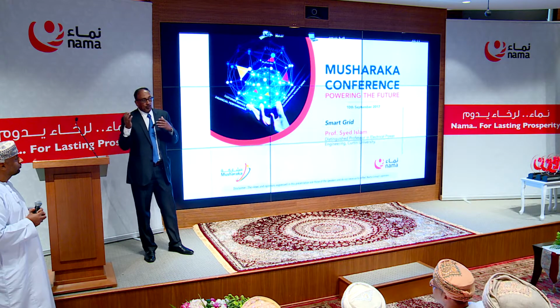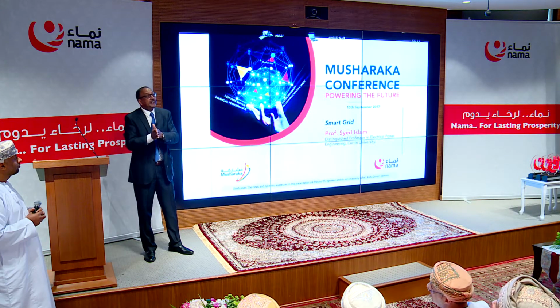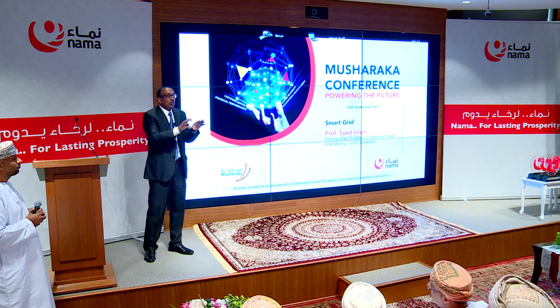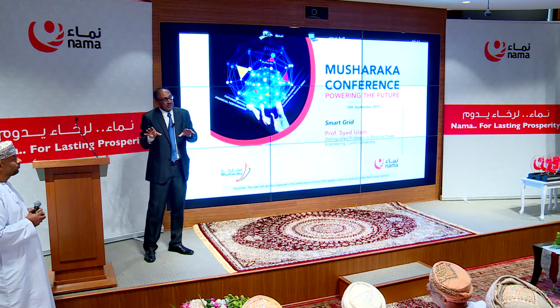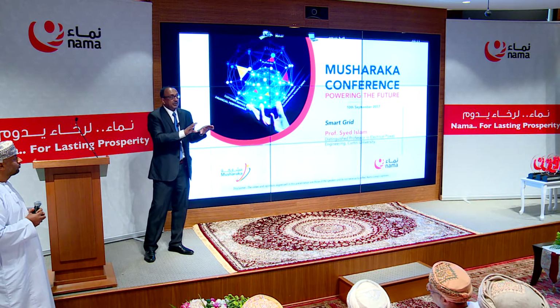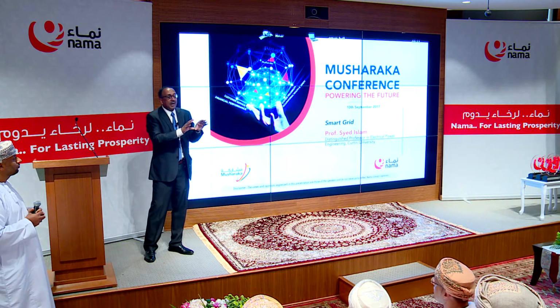Islanding is an issue. For example, if you have rooftop PV and your electricity grid is disconnected, people may go and work thinking the network is isolated, so islanding becomes an issue. As long as you have islanding protection and know your DC side is energized, I think those maintenance and safety issues could be avoided.